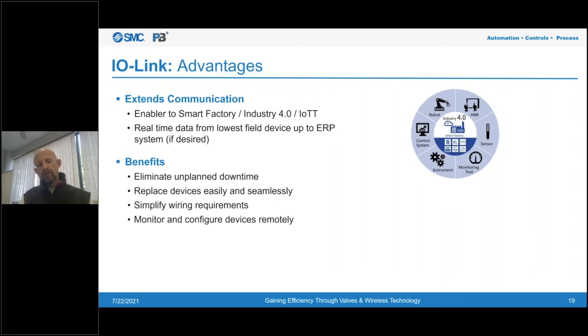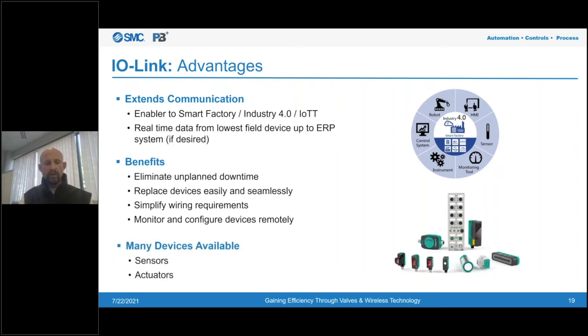Because we're storing all of the configuration and setting information on devices, we can replace an IOLink device with the same device, and the settings and parameters will all get downloaded to that device automatically from the IOLink master. It really reduces setup time for new devices. Because of the M12 wiring, it simplifies the wiring, and we have the ability to monitor and configure devices remotely from the IOLink master.